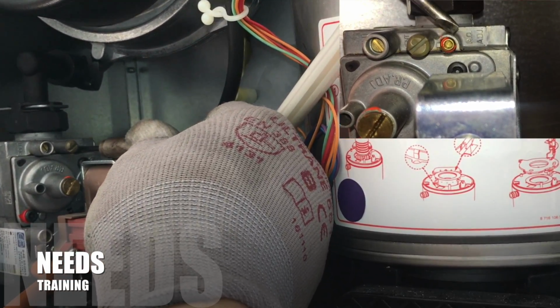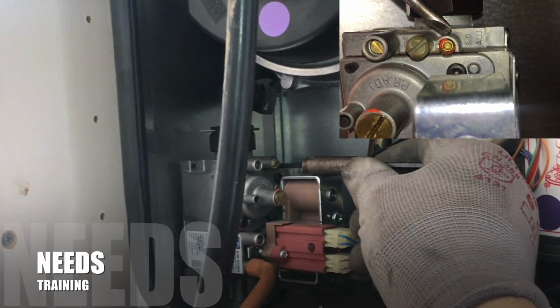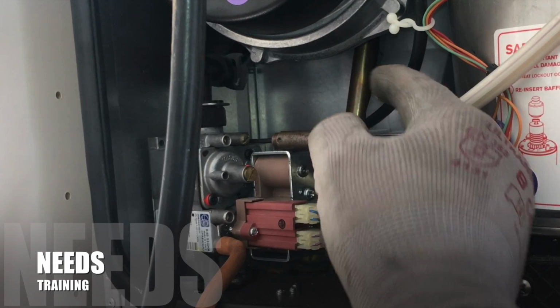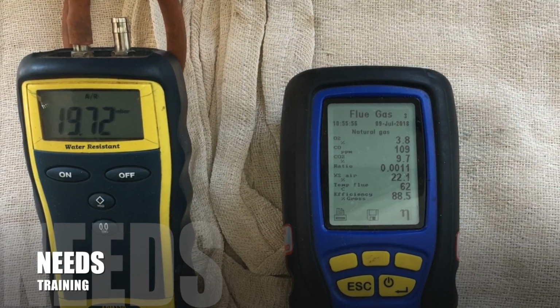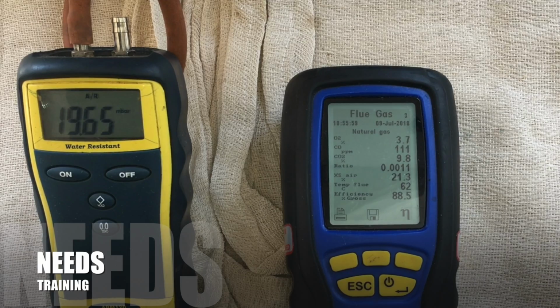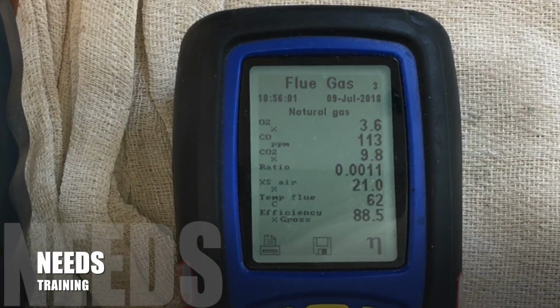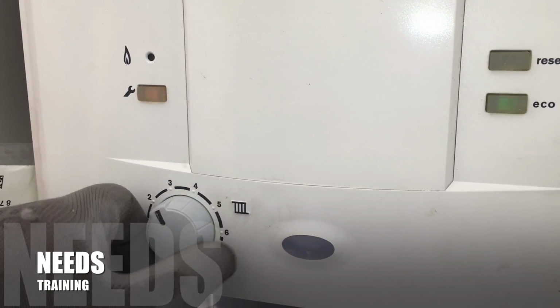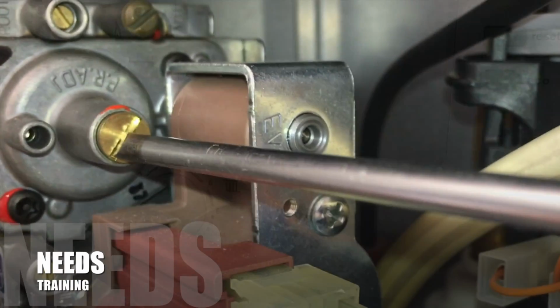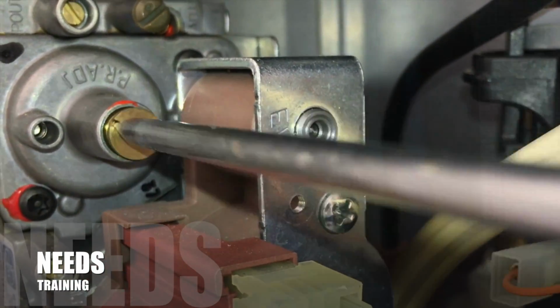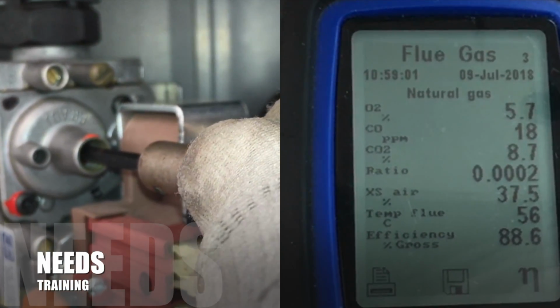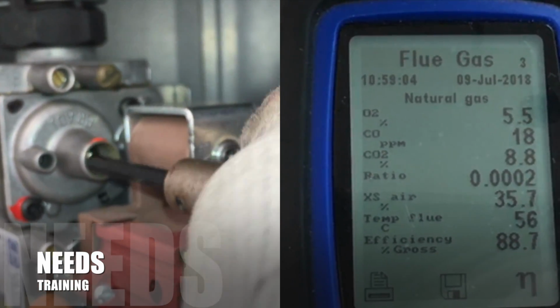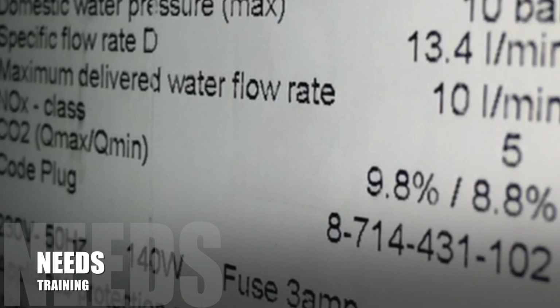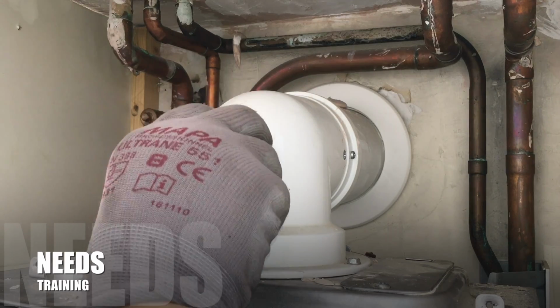To adjust the CO2 readings in high fire, you would need a 2.5mm Allen key. Now turn the heating controls to minimum for low fire. Adjust the low CO2 with a 4mm Allen key. The correct CO2 readings for this appliance are 9.8 high and 8.8 low. Remove the gas analyzer probe and replace the cap.